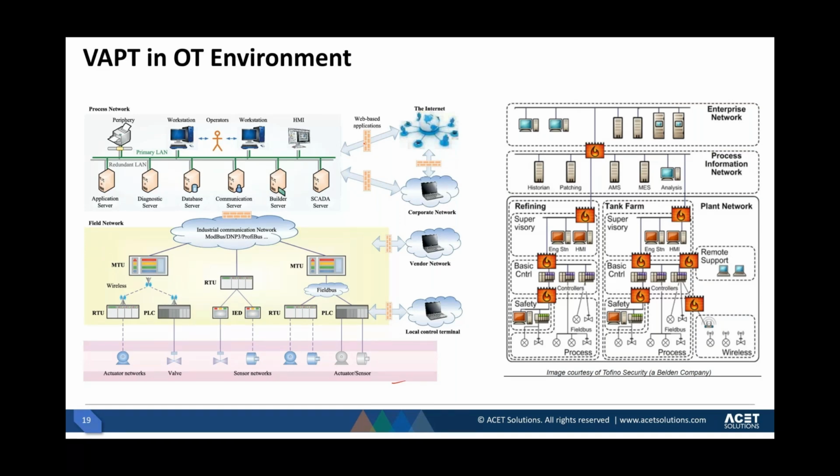I have been involved in a few PT exercises where the project was in the factory acceptance test phase, FAT, and all this equipment is still in the vendor's workshop, or the panel shop, if you may, and they have connected all the networks and all the computers to test it. And yes, the PT can be done in that environment, but still there are limitations because not all the systems are fully operational the way they're supposed to be.